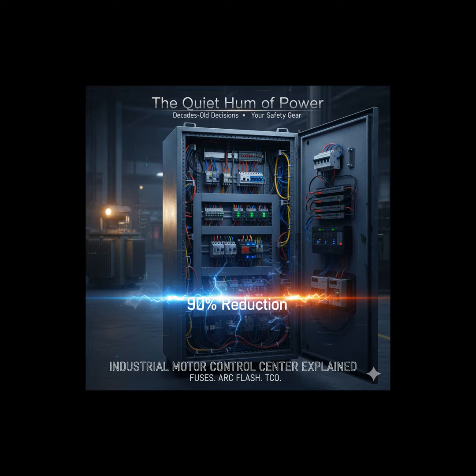And we should be clear. When engineers talk about an MCC, they're referring to a very specific piece of equipment defined by NEMA and UL standards. It's a floor-mounted assembly of these enclosed vertical sections, and they're all unified by a really critical component, the common horizontal power bus. And crucially, it principally contains what we call combination motor control units.